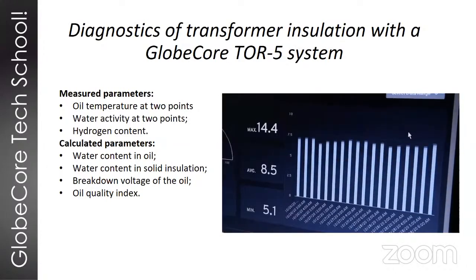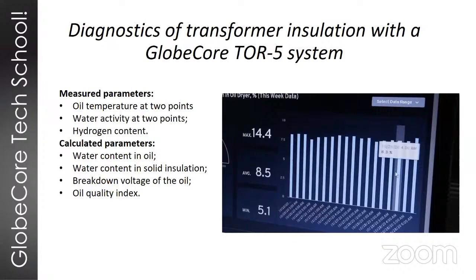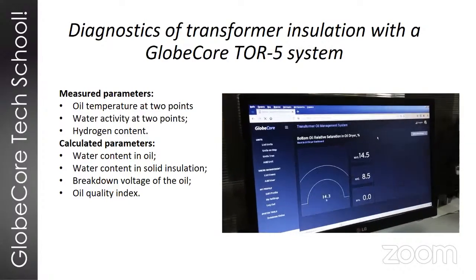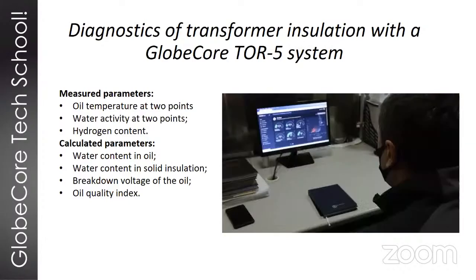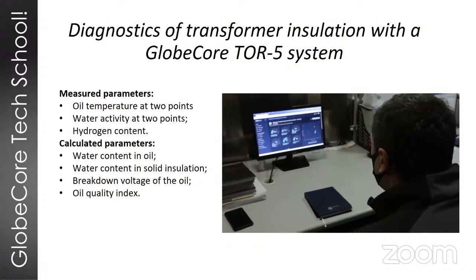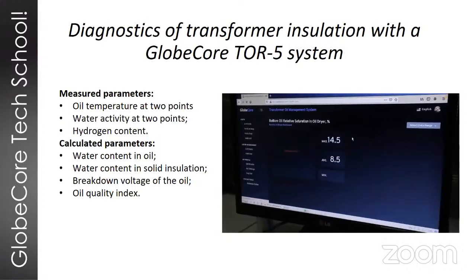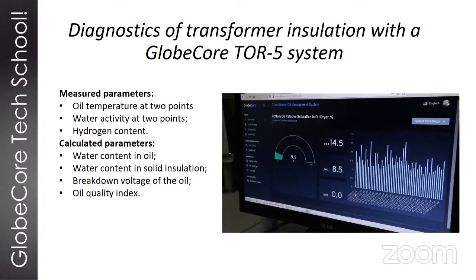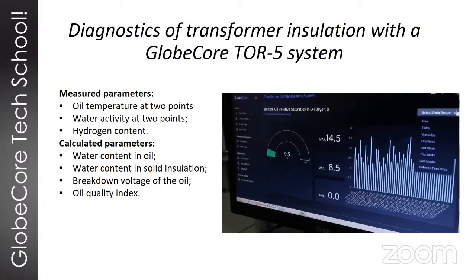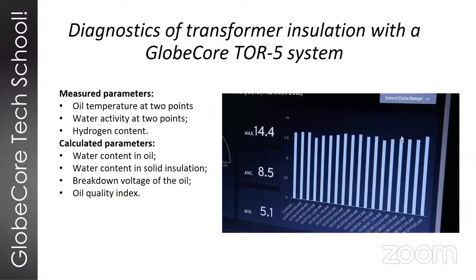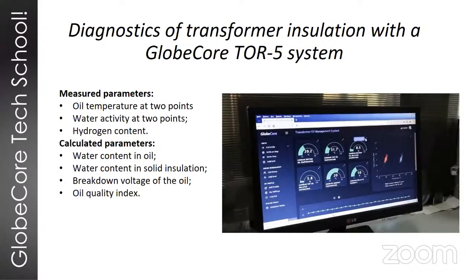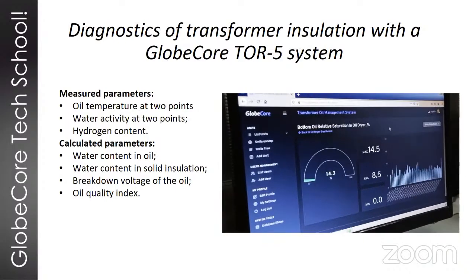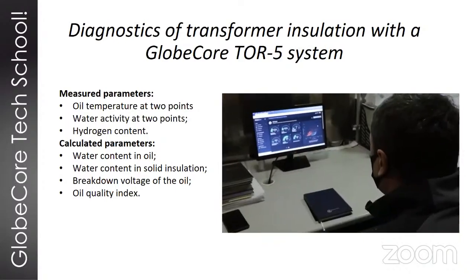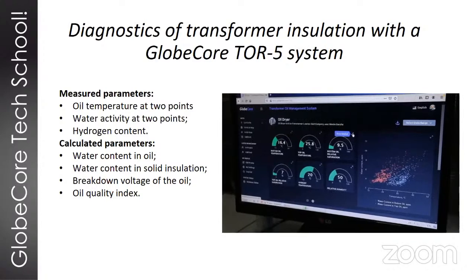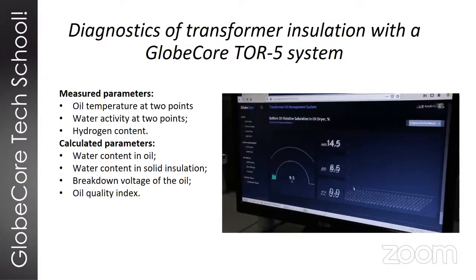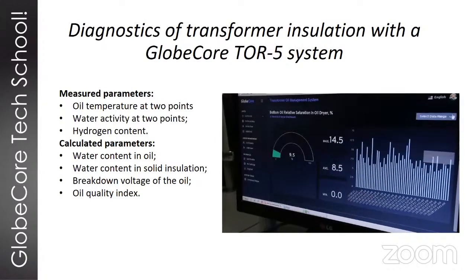So the measurements are transmitted via internet to a cloud server. And in that server, some math happens. There are some formulas that are used to calculate other parameters that will give us a much more complete picture of the transformer condition. And these include the amount of water in the oil in the transformer, the amount of water in the solid insulation, and it also gives us the calculated estimated dielectric strength of the oil as dependent on the solubility of water in the oil.